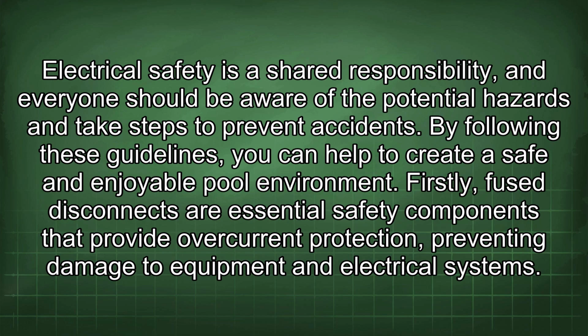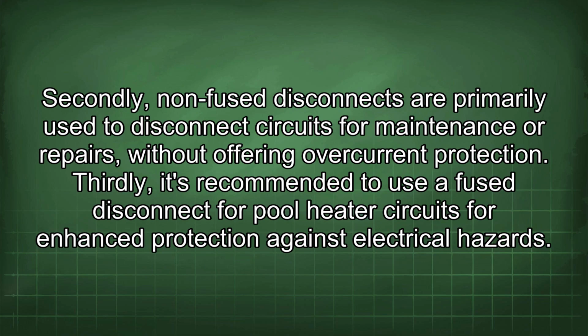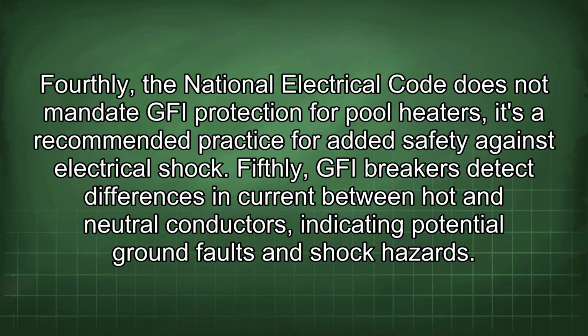Firstly, fuse disconnects are essential safety components that provide overcurrent protection, preventing damage to equipment and electrical systems. Secondly, non-fuse disconnects are primarily used to disconnect circuits for maintenance or repairs, without offering overcurrent protection. Thirdly, it's recommended to use a fuse disconnect for pool heater circuits for enhanced protection against electrical hazards. Fourthly, the National Electrical Code does not mandate GFI protection for pool heaters. It's a recommended practice for added safety against electrical shock.